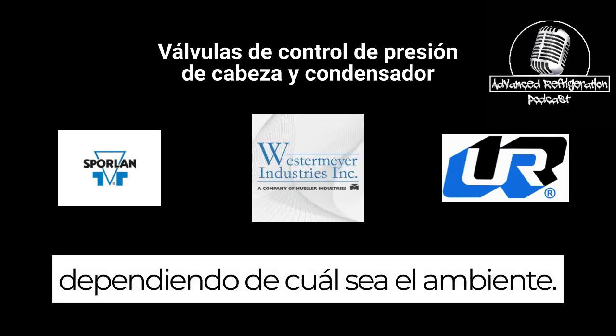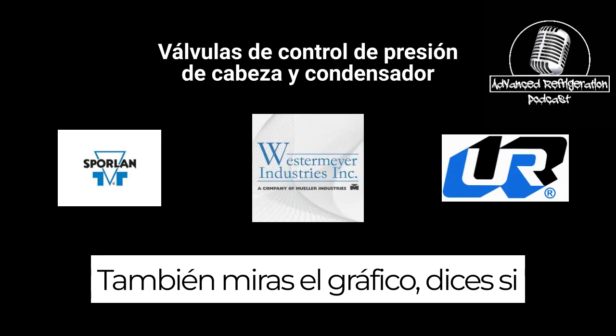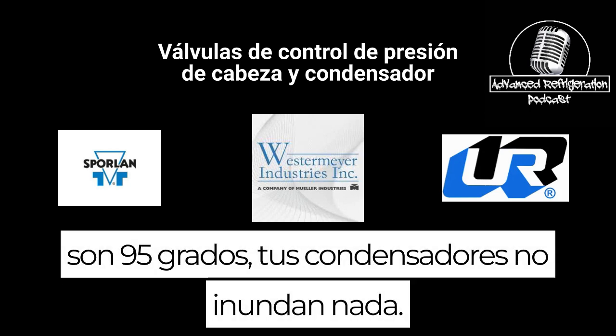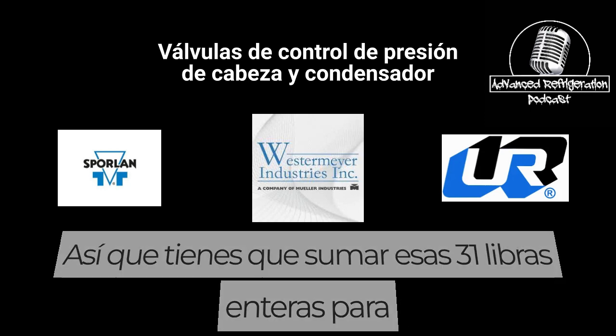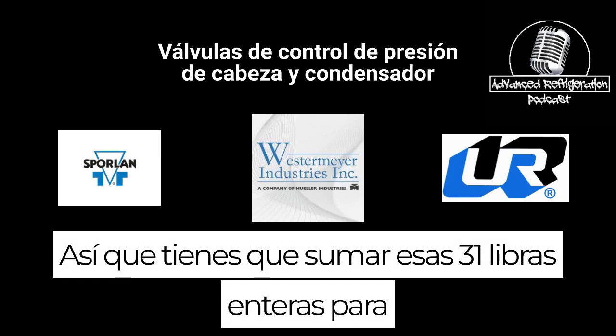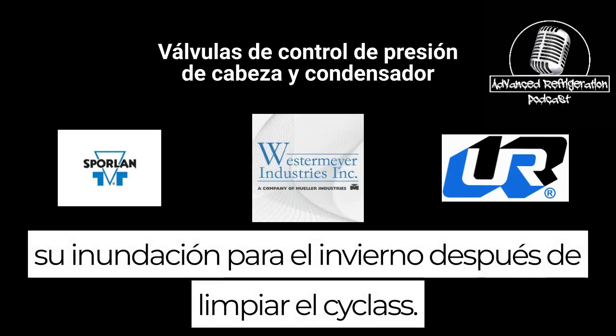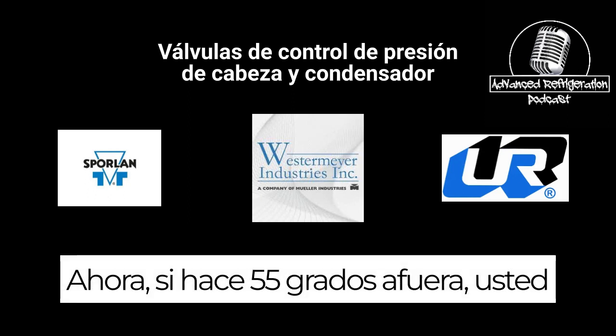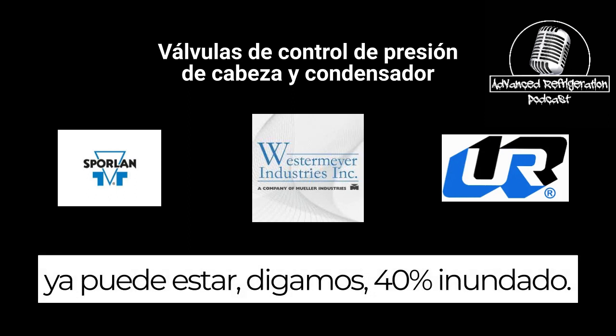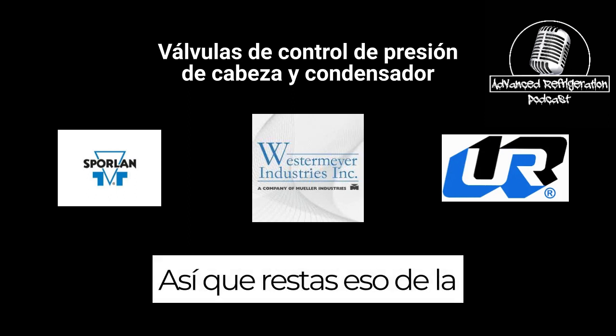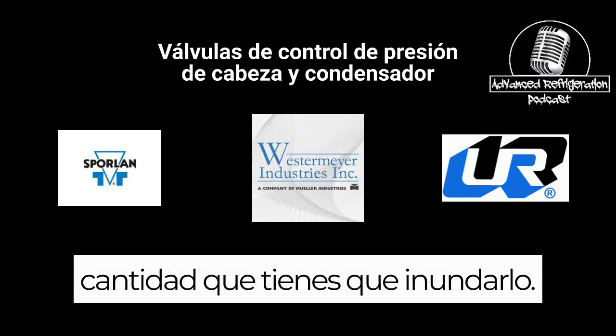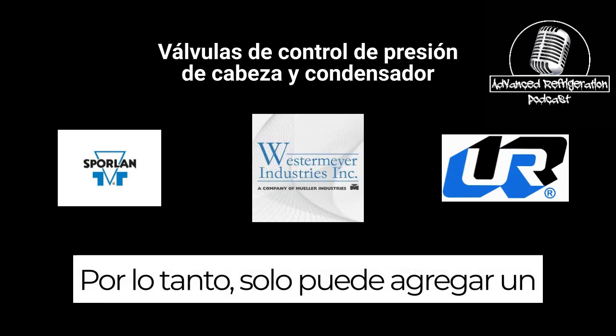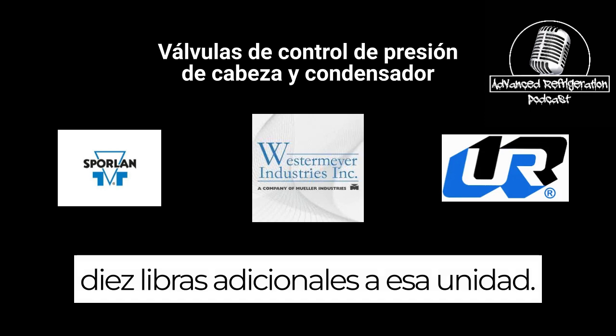Depending on what the ambient is, you also look at the chart. Say if it's 95 degrees, your condenser's flooded nothing. So you have to add that whole 31 pounds in for your flooding for the winter after you clear the sight glass. Now, if it's 55 degrees outside, you may already be, let's say, 40% flooded. So you subtract that from the amount you have to flood. So you may only have to add an additional 10 pounds to that unit.